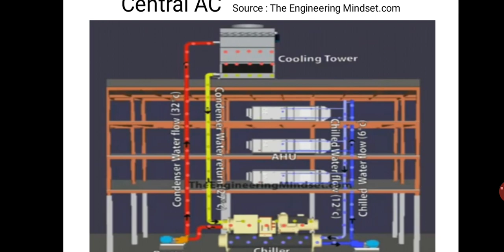You see nowadays they have centralized air conditioning systems. Just to have a fair idea, in the basement you will have a chiller, which contains the compressor, condenser and the evaporator. Now on the rooftop you will have cooling towers. In normal air conditioning, the air is cooled directly in the evaporator and sent to the room, like the split AC we have in houses or bank ATMs. But in this central AC, chilled water is circulated to all the floors. Water is chilled to somewhere around 8 to 10 degrees centigrade in the chiller and sent to all the floors. On all the floors you have something called AHUs, air handling units, which supply the air to all the rooms on the different floors.